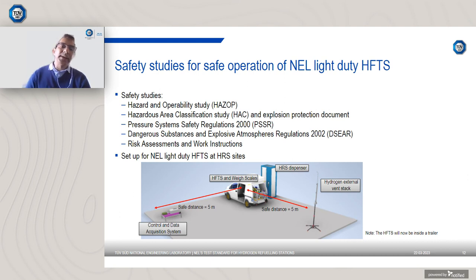The image shown here is a typical setup when we were to be testing at a hydrogen refueling station. Your test standard will be parked right next to the dispenser, similar to how a car would park up for refueling. And you would have the DAQ and control system plus the vent stack a safe distance away from the test rig and the dispenser itself.